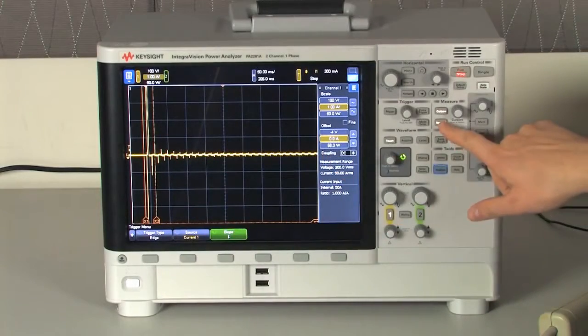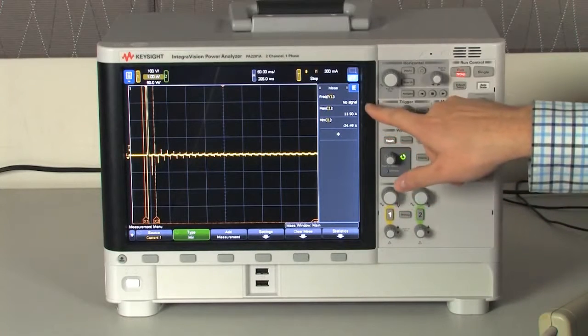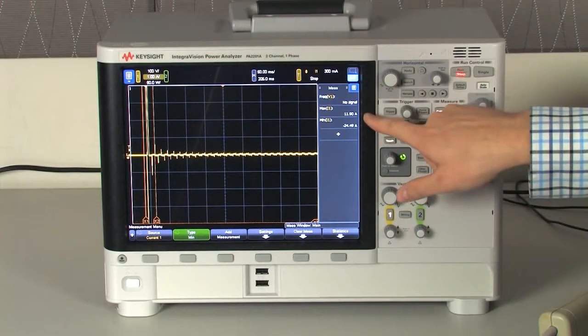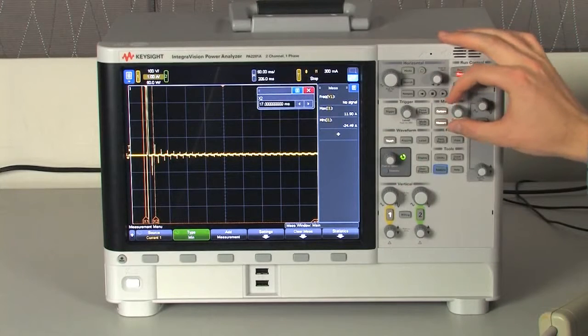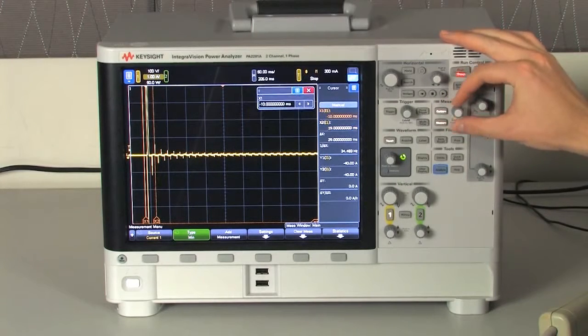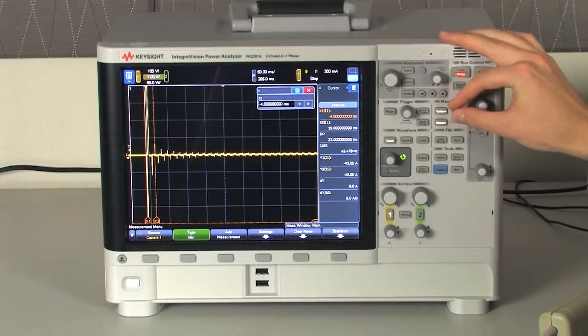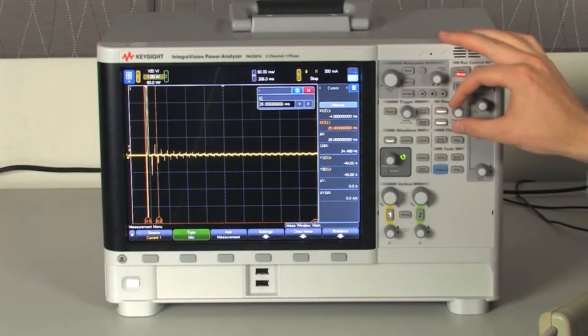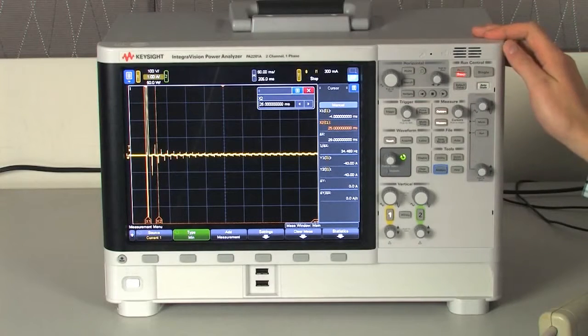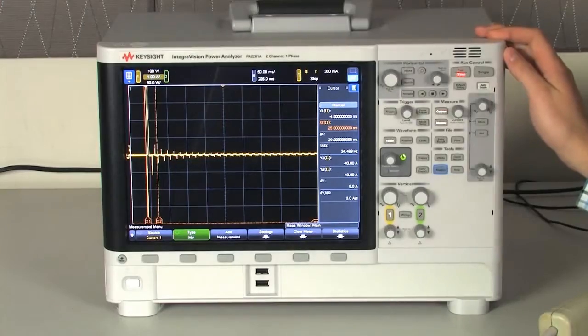So now we can see we had a huge inrush current and then gradually went down to steady state. If I go into the measure menu, I can see what the peak of the inrush current was, and I can use the cursors to measure the time of the inrush current event. As you can see, the scope-like features of this power analyzer make it very easy to measure inrush current.